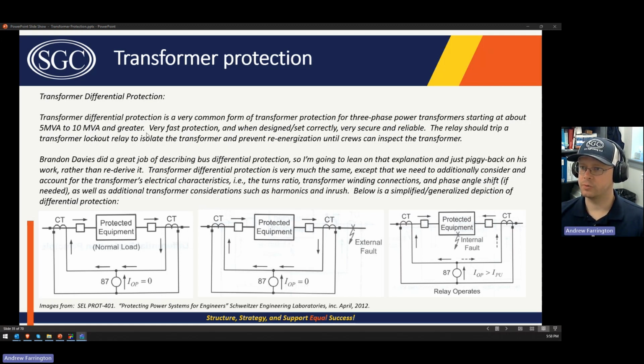Differential protection has some great benefits. It's very fast protection, and when it's designed and set correctly, it's very secure and reliable, so it's very good protection, so we like it. The relay should trip a transformer differential lockout relay that'll be used to isolate the transformer and prevent re-energization until crews can inspect the transformer.